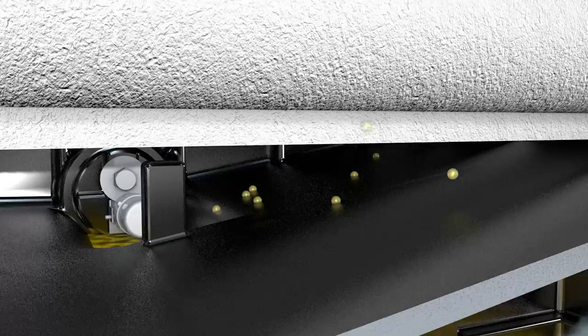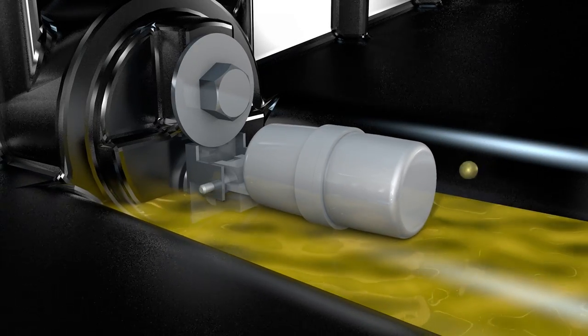Eventually, it leaves the exhaust of the pump. The aerosols condense in oil droplets in the exhaust filter. This recovered oil is collected and sent back to the generator once the float valve opens.